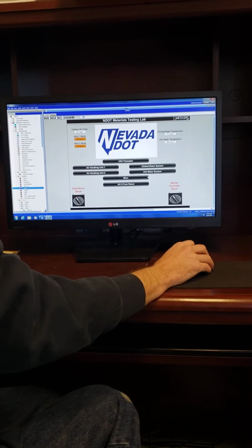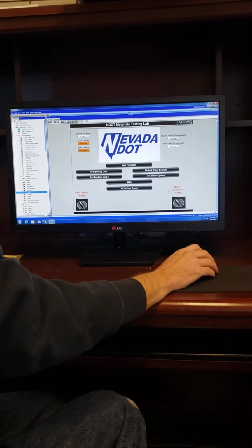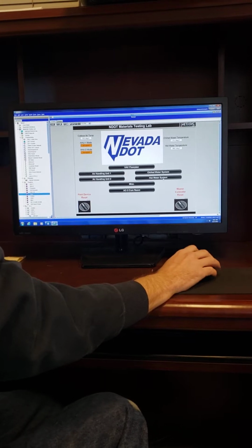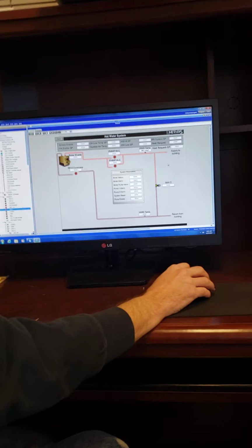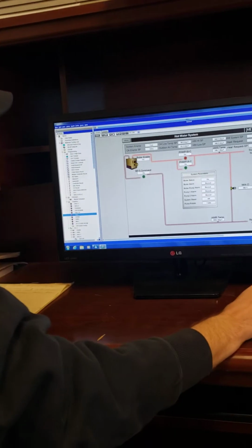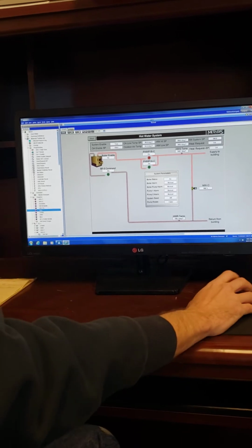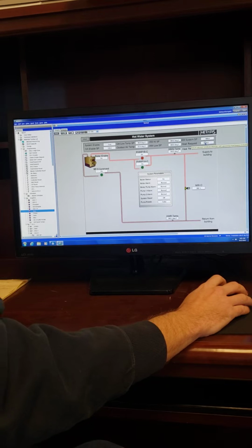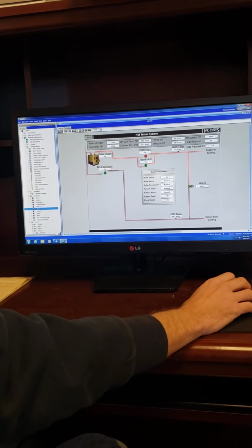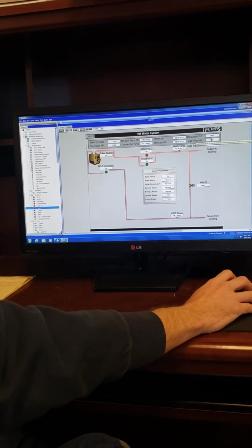First we can go to the hot water system. That's the one you've been having the issues with. Let this load up. Okay, so what I found is what was keeping your hot water system turned off was this heat request and heat request set point. This heat request is essentially saying how many zones in the building require heat.